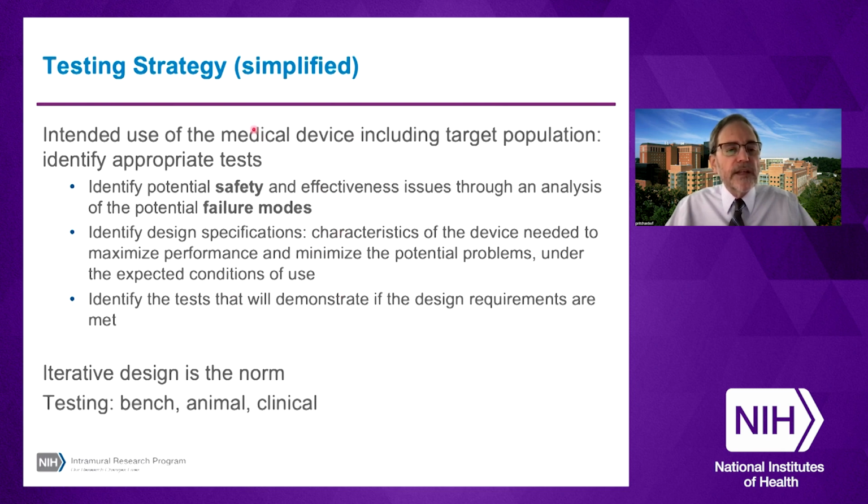So you need to consider the intended use of the medical device, including the target population. Who are you going to be using the device on? To identify the appropriate testing, first of all, you need to identify potential safety and effectiveness issues through an analysis of the potential failure modes.